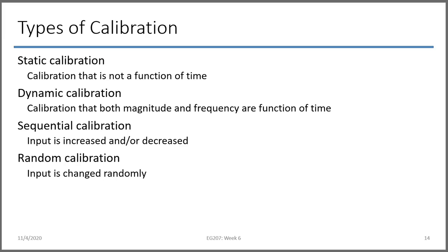So this is where in our calibration we're actually looking at the response versus time of a known type of input. So that input can be sort of an impulse response, where you send a short, quick pulse of information, and then you look at typically, let's say, the voltage response of your sensor, or a step function, where you have no input, and then all of a sudden your input goes from 0 to 1, and then you look at how your sensor actually responds, so that you can get an idea of how it responds to those different inputs and calibrate what the input signal would be based on the time response that you actually see in your sensor.